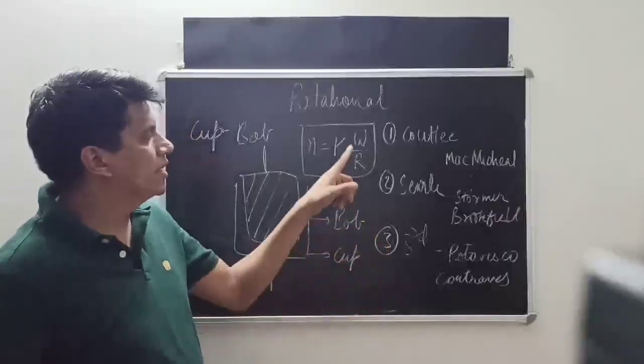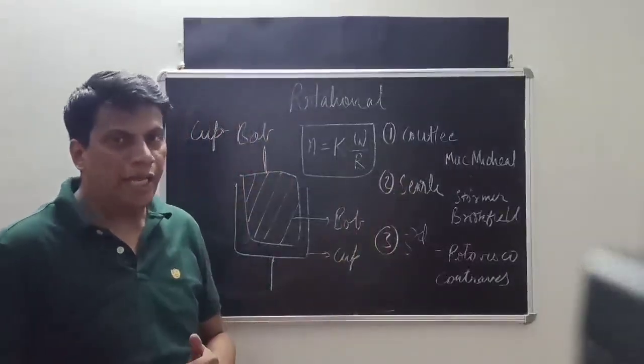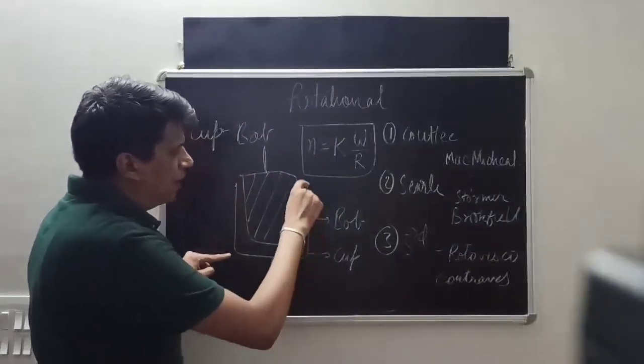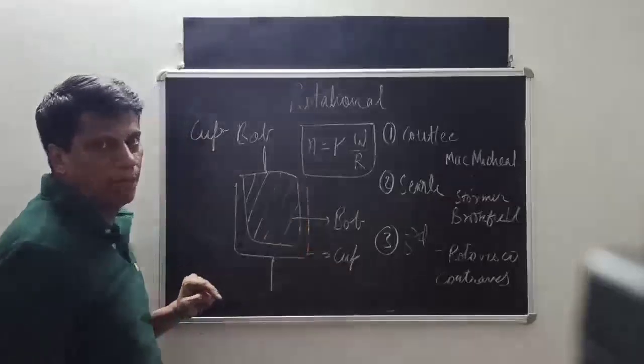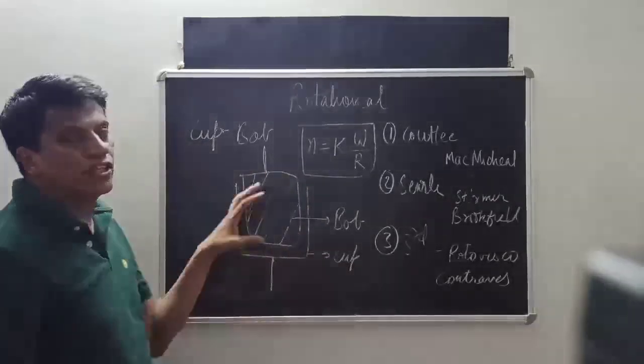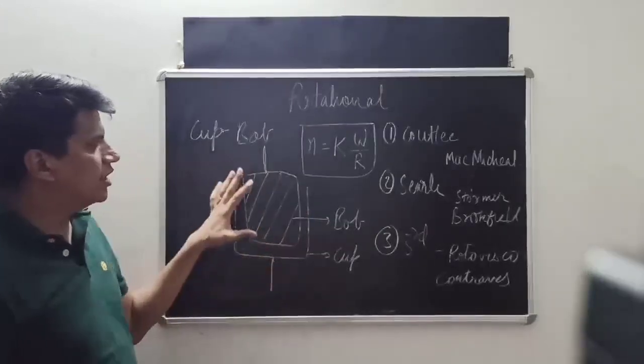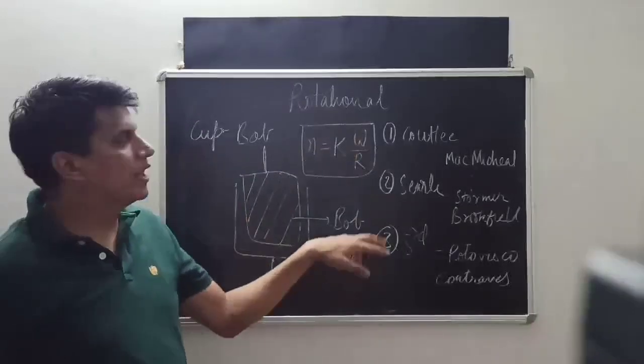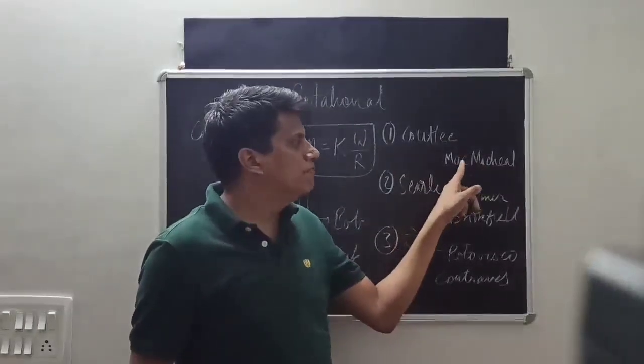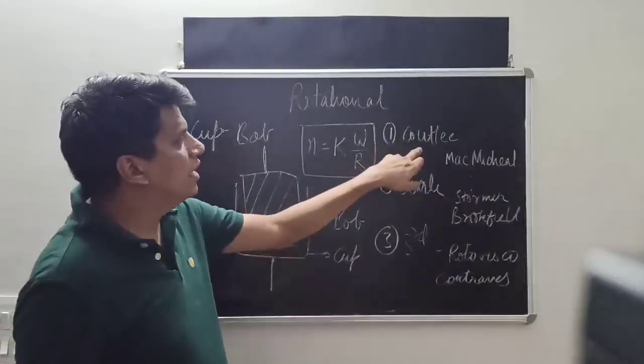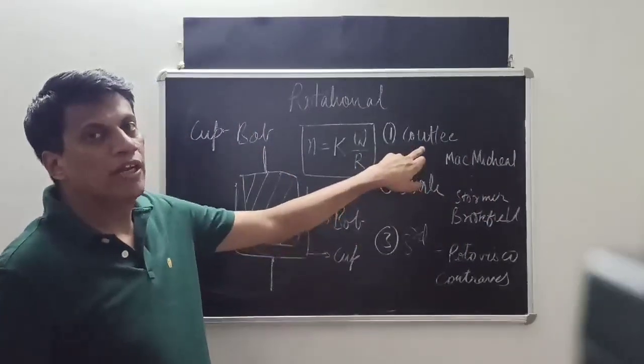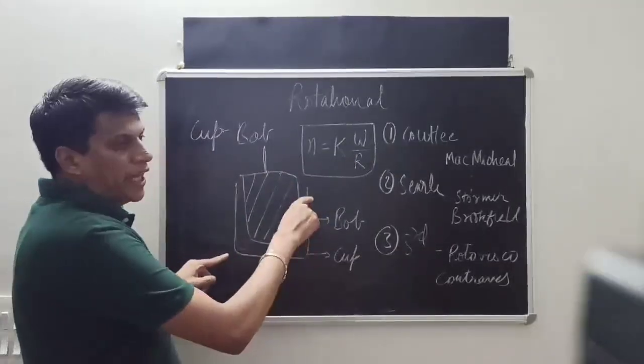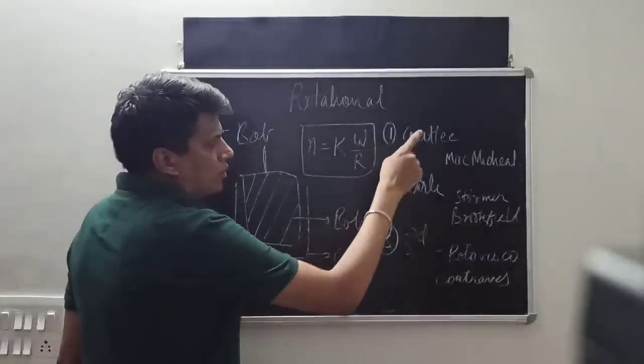Cup and bob viscometers are further classified into three types, but before that let me tell you what is the cup and what is the bob. The hollow cylinder, the outer part, is known as the cup; the inner solid part is called the bob. In this equipment, either the cup rotates or the bob rotates. The Couette type, whose example is the MacMichael viscometer, is the cup and bob viscometer where the cup is rotating and measurement is done on the bob.